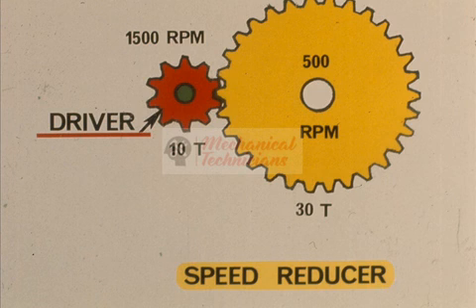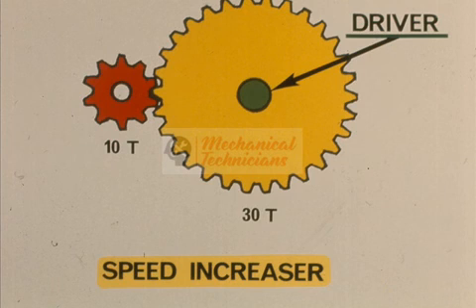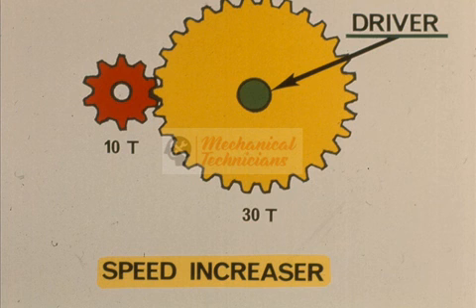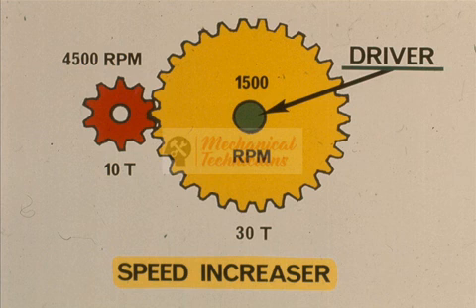If the small gear is turning at 1,500 revolutions per minute, then the large gear will only turn a third as fast, or 500 revolutions per minute. This would be a speed reducer, since the driver is on the high speed shaft. On the other hand, if the driver is coupled to the shaft with the large gear, you will have a speed increaser. In this example, the driver is still turning at 1,500 RPM, but now coupled to the large gear, which turns the small gear three times as fast, at 4,500 RPM.